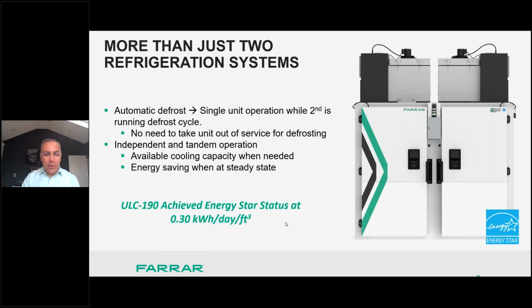So we've talked about dual refrigeration systems, and when you think of redundant refrigeration systems, you think backup in case one goes down. Absolutely true, but we've added additional intelligence that really gives you the cooling capacity and power that you need when you need it. So the first area I want to talk a little bit more about on our ULC is its auto defrost. It's really the hallmark of what we do that really makes us different. Our automatic defrost runs regularly to ensure performance is maintained without icing over.